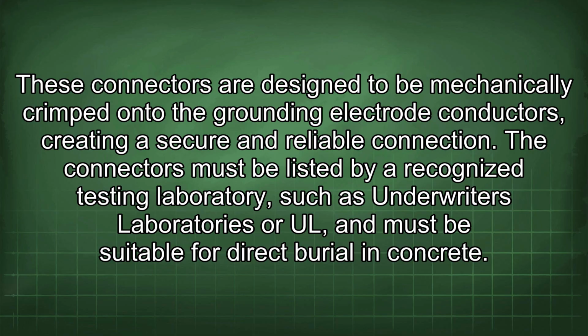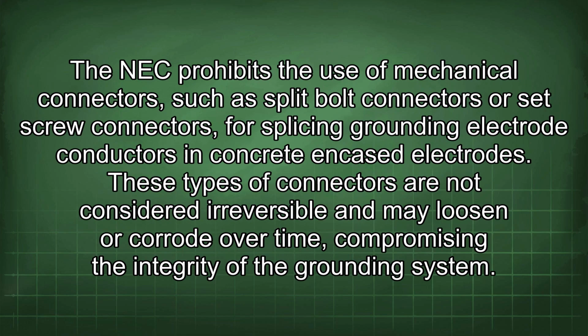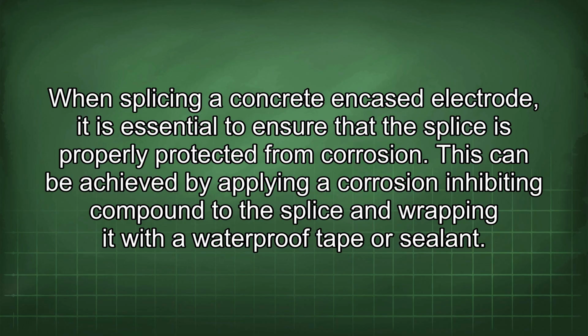The connectors must be listed by a recognized testing laboratory, such as Underwriters Laboratories, or UL, and must be suitable for direct burial in concrete. The NEC prohibits the use of mechanical connectors, such as split bolt connectors or set screw connectors, for splicing grounding electrode conductors in concrete encased electrodes. These types of connectors are not considered irreversible and may loosen or corrode over time, compromising the integrity of the grounding system. When splicing a concrete encased electrode, it is essential to ensure that the splice is properly protected from corrosion.